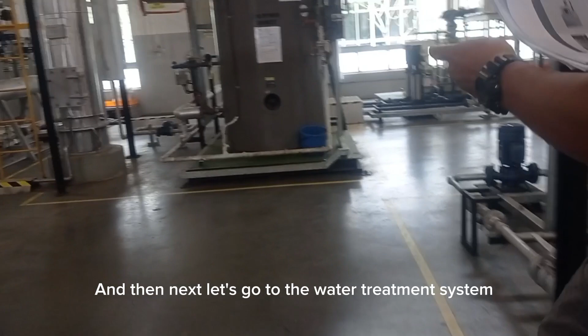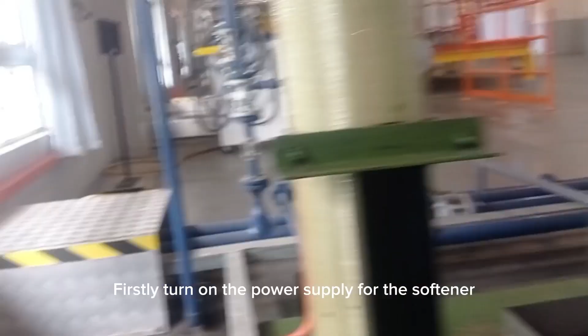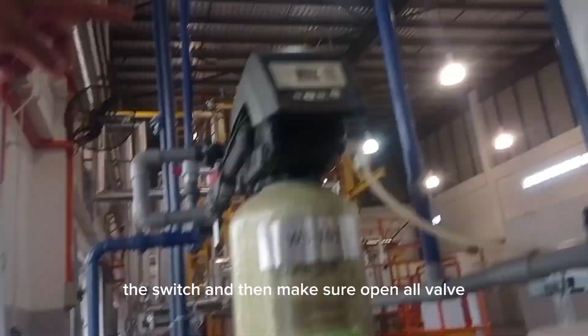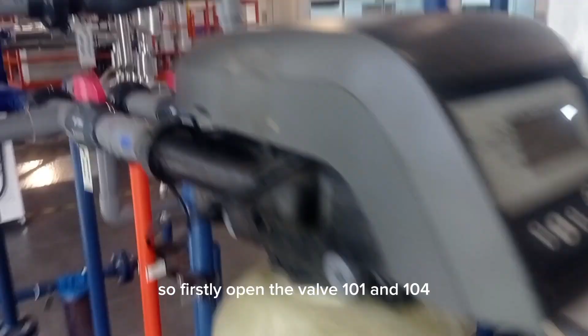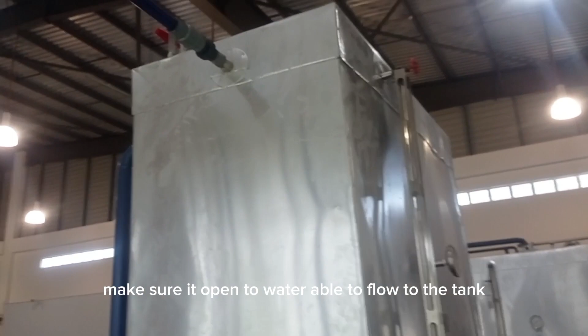And then next, let's go to the water treatment system. Firstly, turn on the power supply for the softener, the switch, and then make sure to open all valves for the water flow. So firstly, open 101 and 104 and then 105, and make sure 103 is off. At the above, there's valve 109. Make sure it is open so water is able to flow to the tank. Then after all the valves are on, water is on standby to use. So before running the boiler, we must ensure all the valves are on.